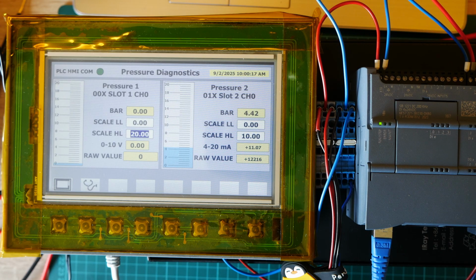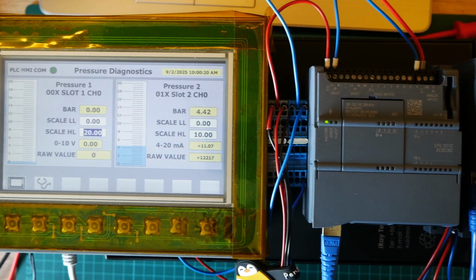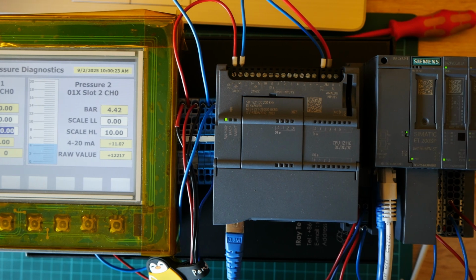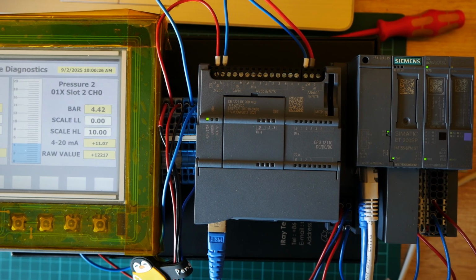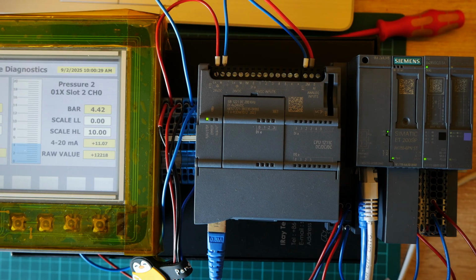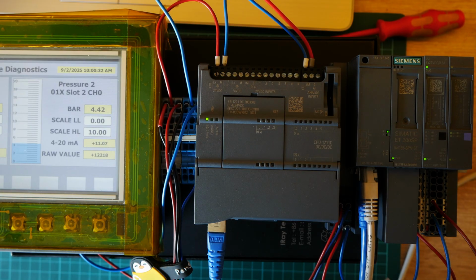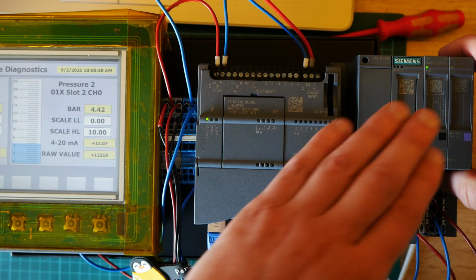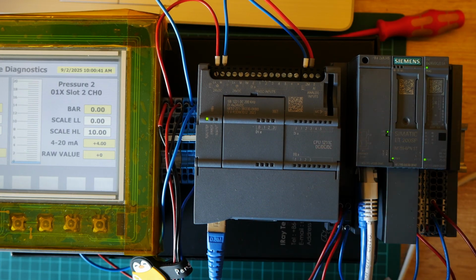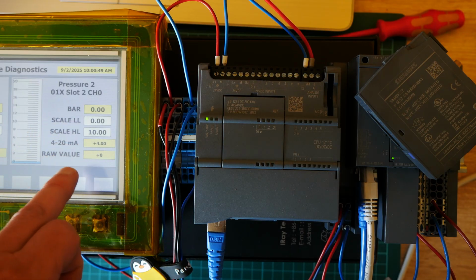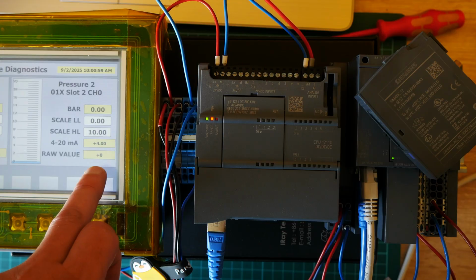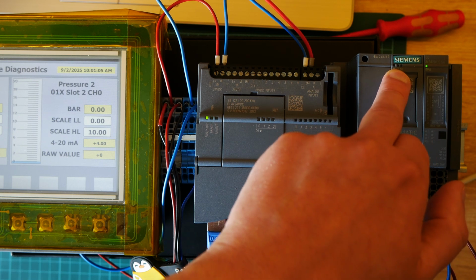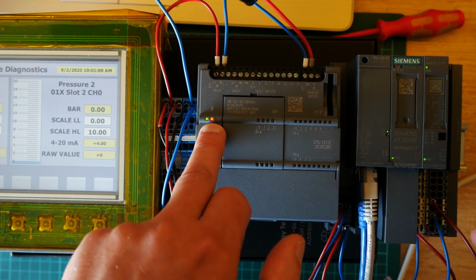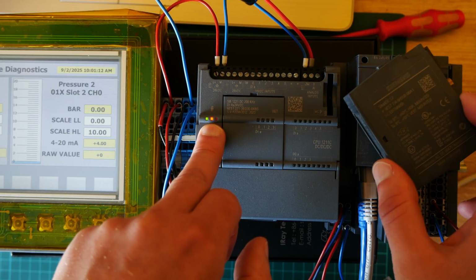Now another thing could be that sometimes, if your environment vibrates a lot, with something pressing or hitting, it's very unlikely, but you could have a bad contact on this analog input card. So I will remove it completely. What you should expect is that the raw value should be 0.